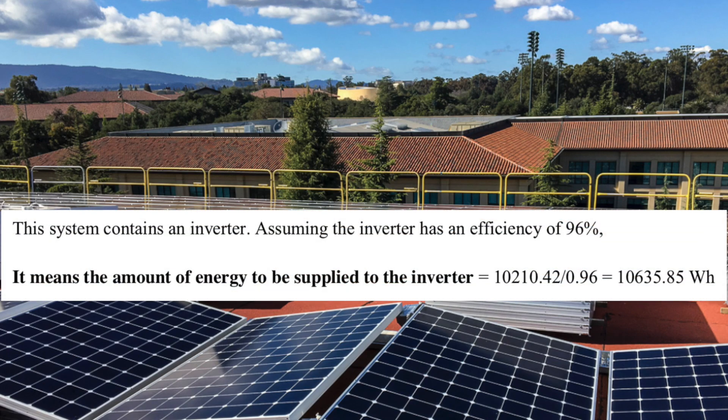Now that we have calculated the amount of energy we want from our system to give us two days autonomy and power our appliances in 10 hours, we can calculate the capacity of each component. Remember the inverter is connected directly to the electrical appliances, so going up from the electrical appliances to the solar panels, the next component is the inverter. We can assume our inverter has an efficiency of 96%. The storage autonomy value calculated was about 10,210.42 Wh, so we divide by 96% to get the capacity of the inverter, which is 10,210.42 Wh divided by 0.96.